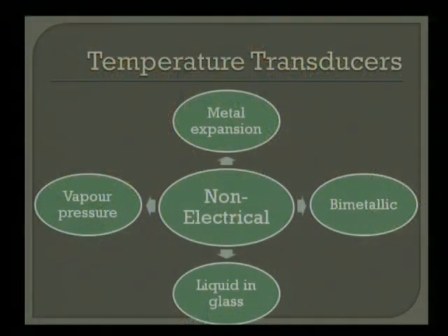So instead of directly measuring temperature, we expose a closed system to a temperature-prone zone, the thermal energy is transferred to that particular system, and a larger pressure is generated inside the system. So ultimately we are measuring pressure, but we are reading it in terms of temperature. Larger the temperature, larger the pressure, and that larger pressure you are reading in terms of temperature. So ultimately the relation that we are utilizing is that pressure is proportional to temperature, in order to measure the temperature.